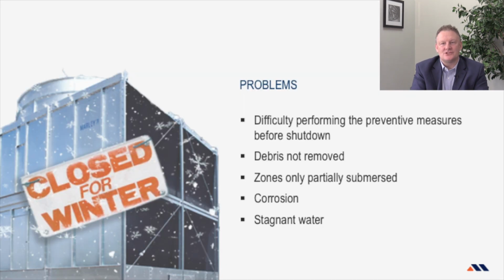Some preventative measures can reduce the inconvenience associated with cooling system stoppages. However, it's often difficult to plan these as it's dependent on our ever-changing weather. These spontaneous stoppages prevent the proper removal of debris, thus allowing the debris to build up in different areas of the system. It's also important to consider that seasonal cooling towers, when stopped, are often only partially emptied.